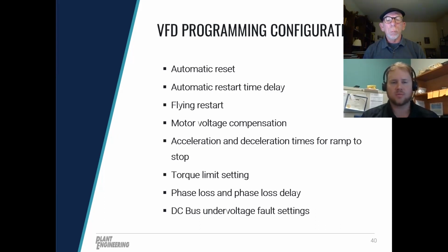And then, of course, the basics: phase loss, what happens upon phase loss, and phase delay settings. Basically, what does the drive do when it sees that DC bus voltage drop, and how fast does it respond to that? Really, all of these parameters and some programming techniques can help mitigate nuisance trips and help with ride-through. But of course, just keep in mind, if the drive sees 20% voltage or something like that, that's extremely low, there's not really much you can do. That's going to affect you. That's going to affect all the facilities around you.